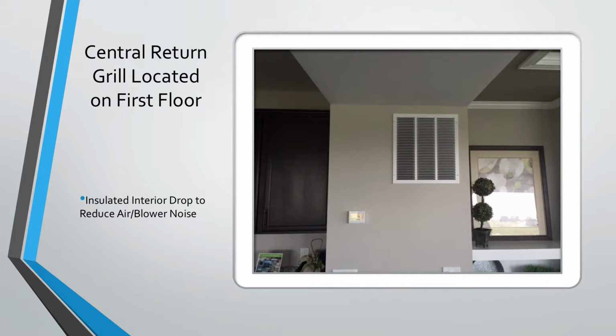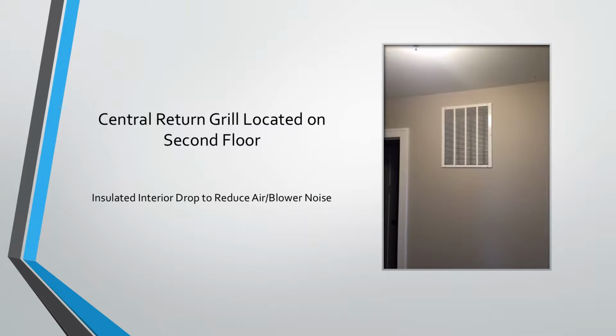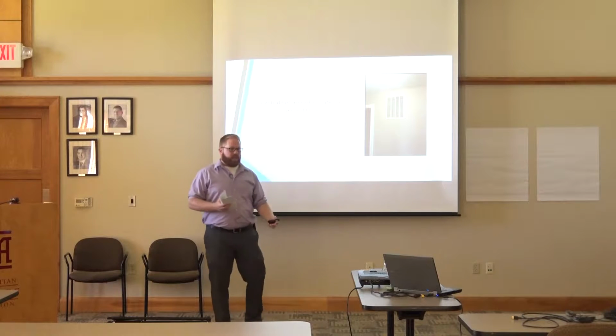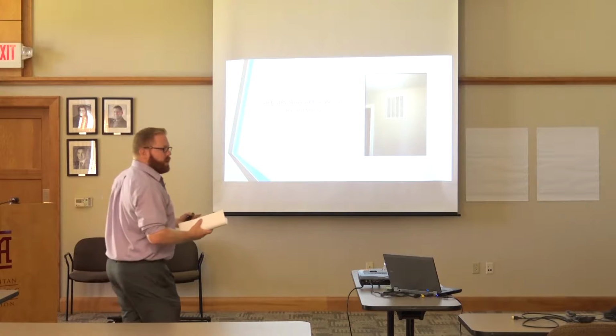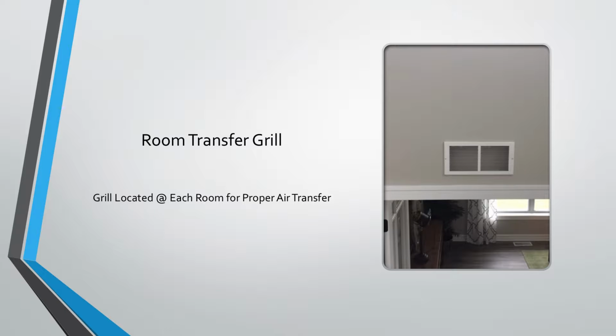This is a particular application for a central return grill located on the first floor. There's a chase for the ductwork built right here for that central return, and then that chase extends up to the second floor as well. The best locations for those are typically hallways and rear foyers, keeping them away from bedrooms, living rooms, and great rooms to cut down on noise. Then for each individual bedroom, there's a transfer grill typically located above the doorway.